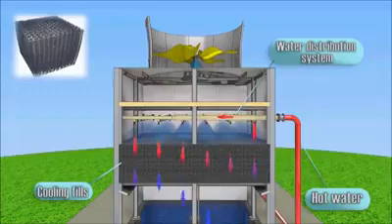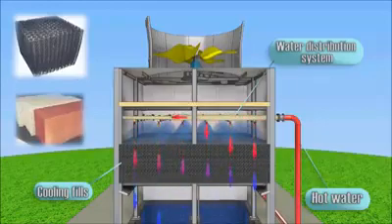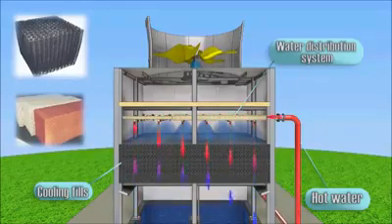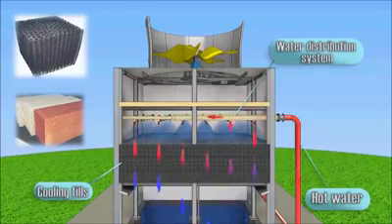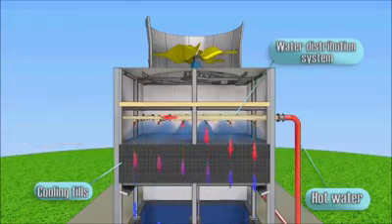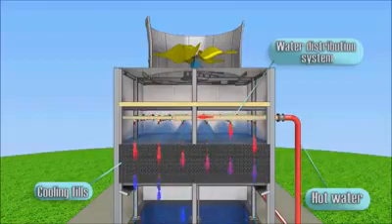On the fills a water film is formed, from the surface of which the water evaporates, encountering the airflow. The larger the surface area of the fills, the more intensive the evaporation of water, and the more efficient the cooling tower.